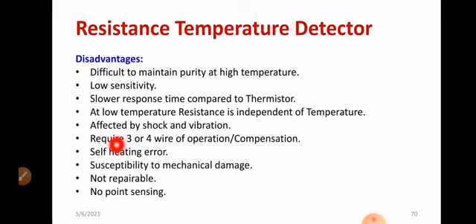And also there are certain setbacks, like being affected by shock and vibration. That is another con. And it requires 3 or 4-wire compensation for a better result. Otherwise, if you go for 2-wire compensation, it is cheap, but I won't get a suitable result. It is better to go for either 3 or 4-wire compensation. Self-heating error is another issue, so you'll be getting a wrong reading. However, it is accurate, but still there is a problem of self-heating error. A suitable heat sink needs to be arranged. Susceptibility to mechanical damage, shock and vibration will directly influence the performance of R.T.D. That has to be taken care of. It is not repairable, just like use and throw. No point of sensing. So these are the few setbacks of R.T.D.